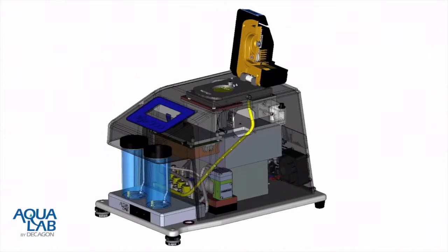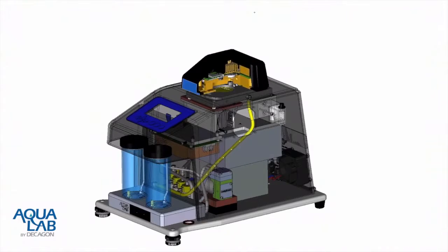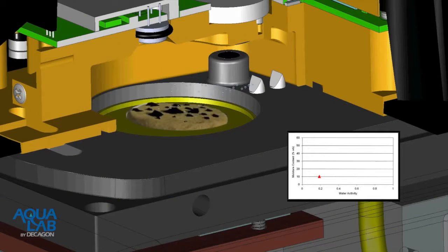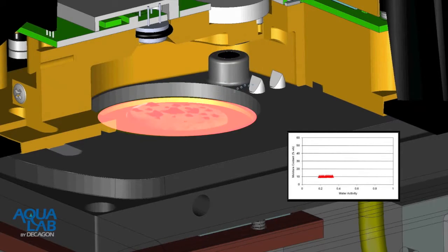The DDI method is a truly dynamic method and produces dynamic isotherms. For this method, instead of holding a sample at a given humidity until equilibration, the sample is exposed to saturated wet air for adsorption and desiccated dry air for desorption. As the sample dynamically takes up or loses moisture, the change in humidity is determined directly using a dew point sensor and the weight change is tracked with a precision balance.